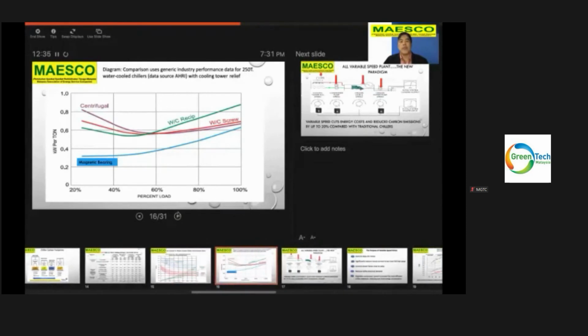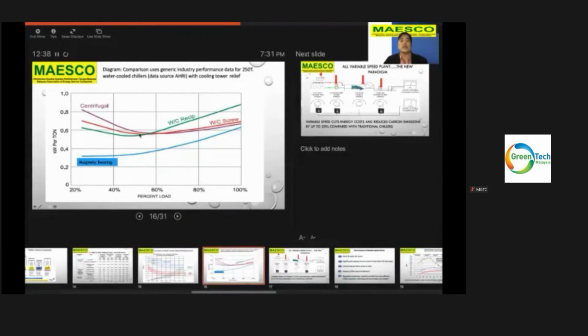And this is another chart. This another chart will tell you, okay, what's the difference? A centrifugal chiller, a reciprocating chiller, screw chiller, centrifugal and magnetic bearing. And if you look at the percentage here, percentage loading against kilowatt per ton, if you notice centrifugal, reciprocating, screw, as you go lower, if you buy a chiller and you operate below 50%, it has no benefit for you. Your kilowatt per ton will go up instead of going down. So do not buy a chiller and run it at part load. They are not designed for that kind of application.